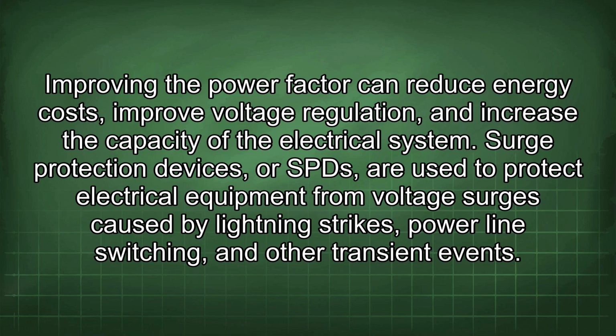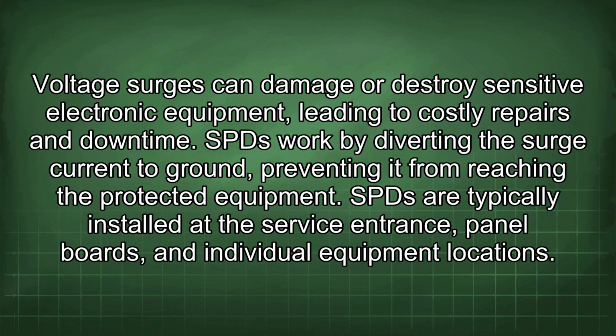Surge protection devices, or SPDs, are used to protect electrical equipment from voltage surges caused by lightning strikes, power line switching, and other transient events. Voltage surges can damage or destroy sensitive electronic equipment, leading to costly repairs and downtime. SPDs work by diverting the surge current to ground, preventing it from reaching the protected equipment. SPDs are typically installed at the service entrance, panel boards, and individual equipment locations.